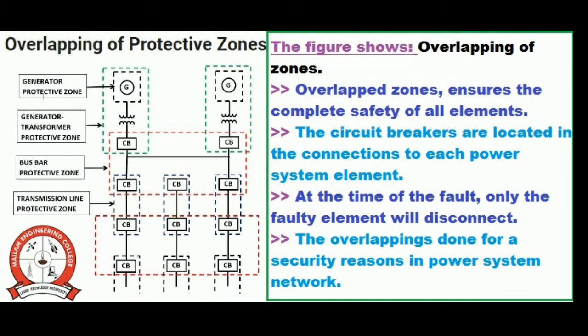The circuit breakers are located in the connections to each power system element so that at the time of a fault, only the faulty element will disconnect. Due to overlapping of the protective zones, if a fault occurs in the overlapped area, more circuit breakers than the minimum necessary will operate. This creates a chance of unnecessary tripping of breakers. However, for security reasons, overlapping is still done in practical power system networks, as there are very few chances that a fault occurs in the overlapped area.